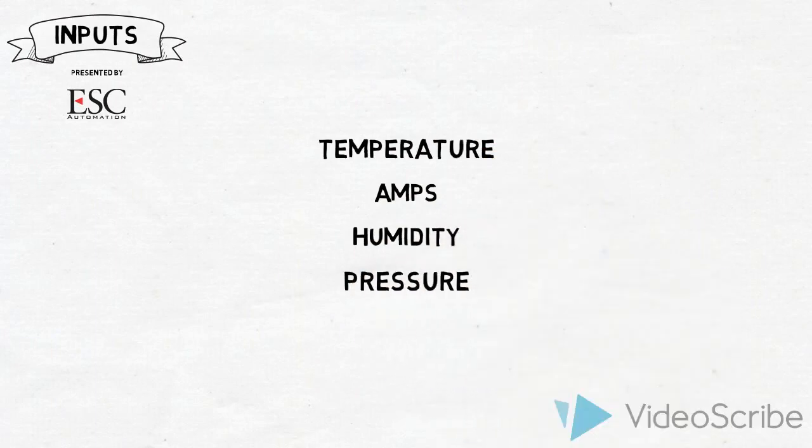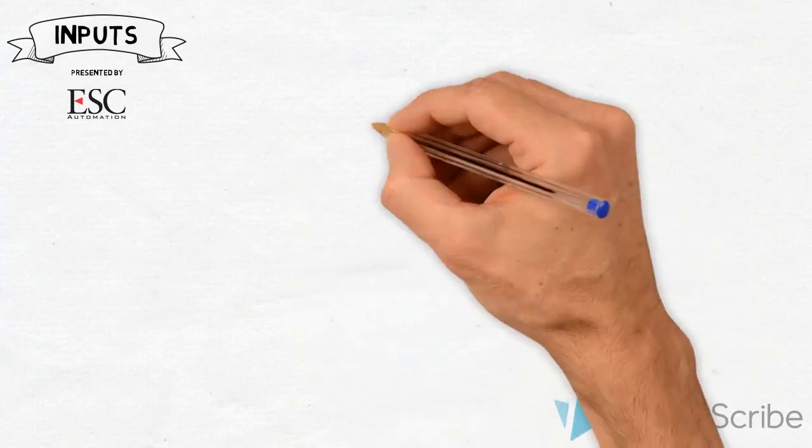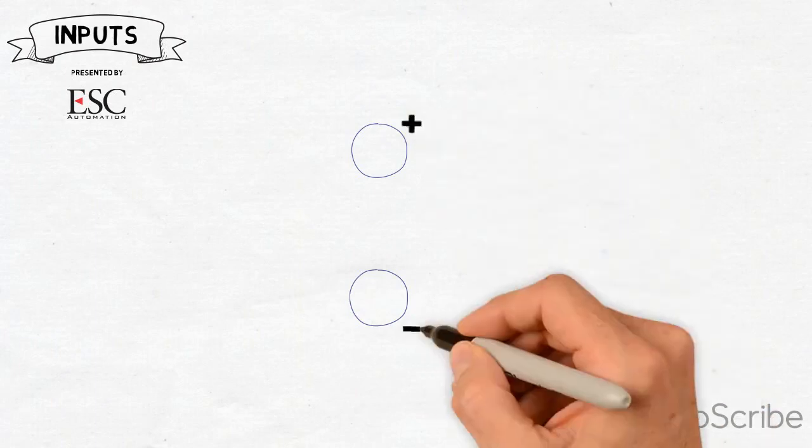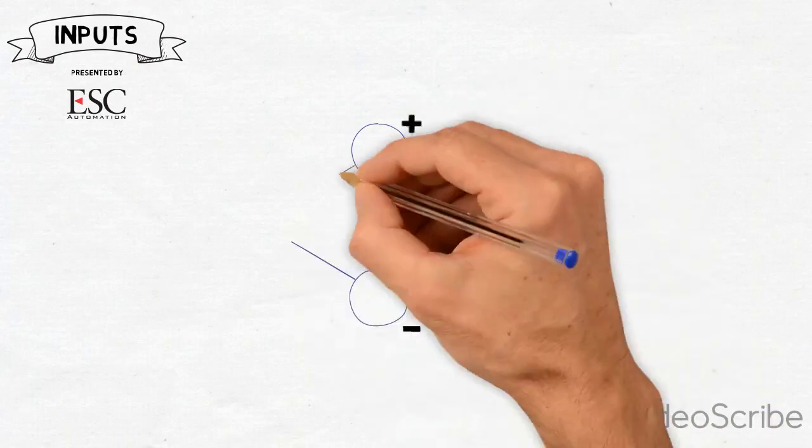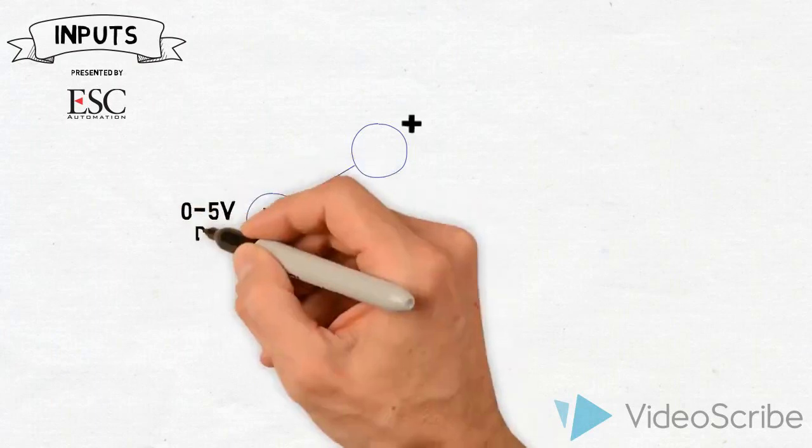There's about five or six different ways they get wired into a panel. A panel input is basically a positive and negative terminal, and the input has a voltmeter on it that reads voltage across the input. The voltage will be between zero and five volts DC.